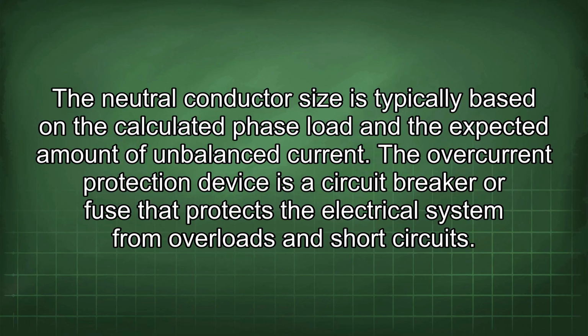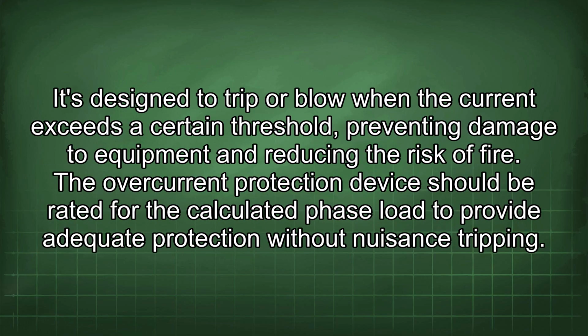The overcurrent protection device is a circuit breaker or fuse that protects the electrical system from overloads and short circuits. It's designed to trip or blow when the current exceeds a certain threshold, preventing damage to equipment and reducing the risk of fire.